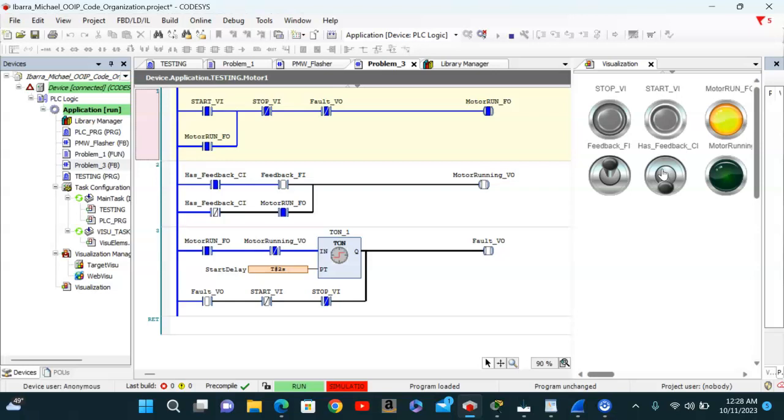In the default position, which is everything off, when feedback is turned on, it ignores the has feedback and it will stay on. As it says in our default, it will ignore the feedback input and assume that the motor is running, so status matches the run output. So flipping this on and off completely ignores it. It won't even tell, and that's because the feedback is on.